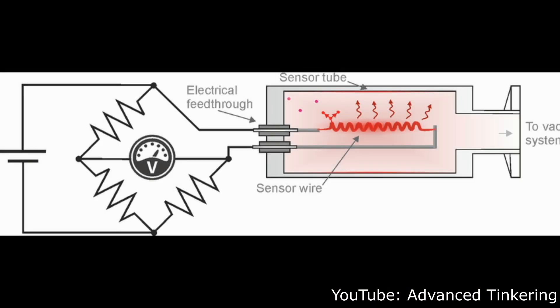The measuring method of a Pirani gauge is in theory pretty simple. It is a heated metal wire that is suspended in a gas and will lose heat when a molecule hits it and carries the heat away from it. That means that in a high-pressure environment there are more molecules that are able to hit the wire and carry the heat away, and in a low pressure environment, a vacuum, there are less molecules that can hit the wire and carry the heat away.